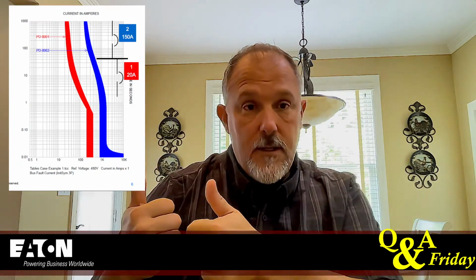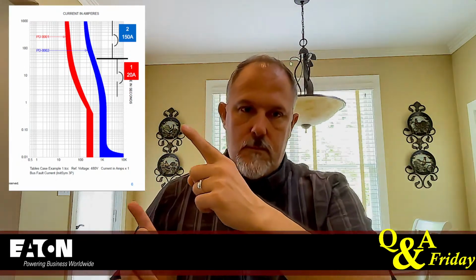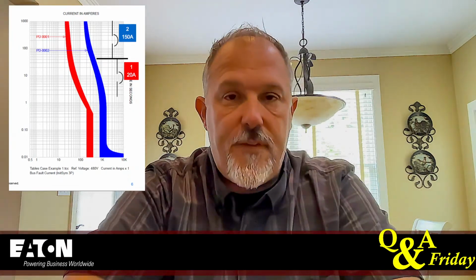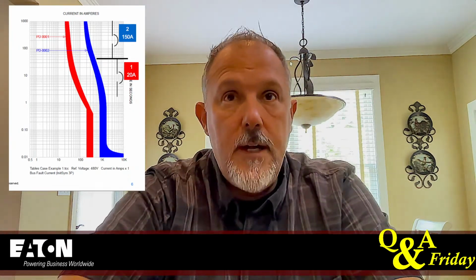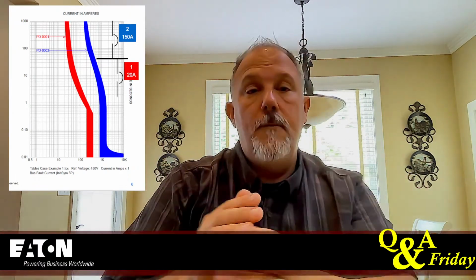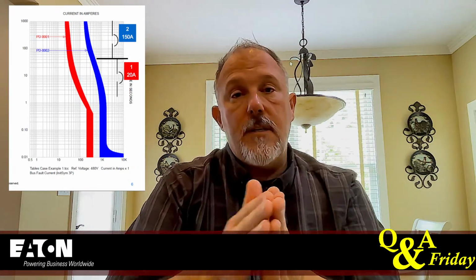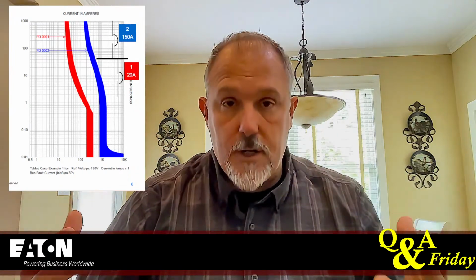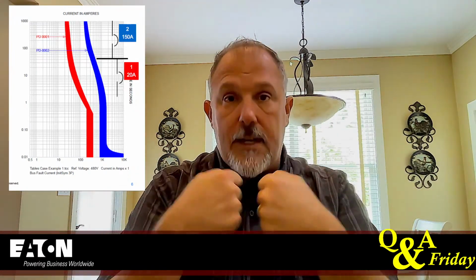Okay, so what do I do to solve this? What do I do if I've got, let's say, 5,000 amps and I've got this problem going on? You've got a couple options. A, you can focus on the upstream device, that F150, the circuit breaker, not the truck. You can make a larger device because the problem is the instantaneous, right? As the fault currents go higher, you're into the instantaneous regions of both the downstream and the upstream device, so they're both going to go. What you want is that upstream device to hold its contacts closed.